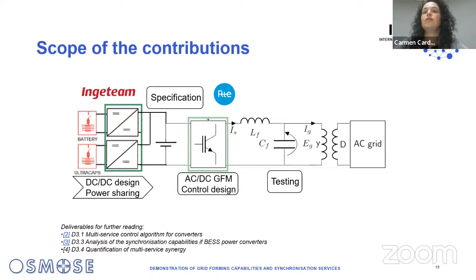So with Ingeteam, we worked basically in a first stage on the specification of what this grid forming capability is. Then, as I said, there was a control development part, not only on the grid forming AC-DC converter, but also on how to handle the DC power sharing on the DC side when we are in a hybrid setting. And of course, it was really important to test the performance of this device when submitted to disturbances of the grid like faults.